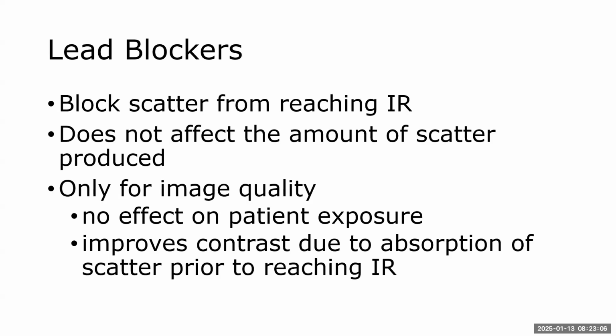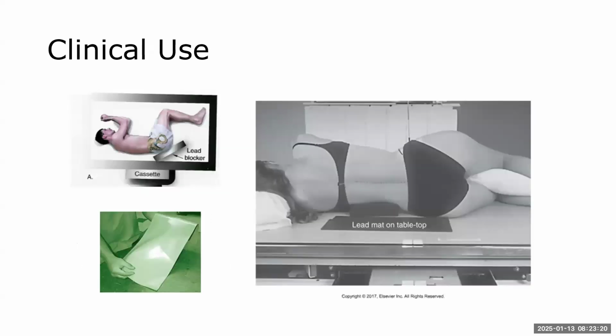So lead blockers block scatter from reaching the IR, but do not affect the amount of scatter produced. It's only for image quality. There's no effect on the patient's exposure, but it does improve contrast due to absorption of the scatter prior to reaching the IR. So let me show you. There are 3 different pictures here just to help show you what's going on.